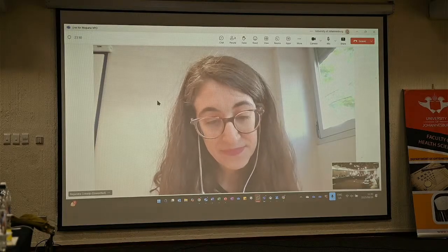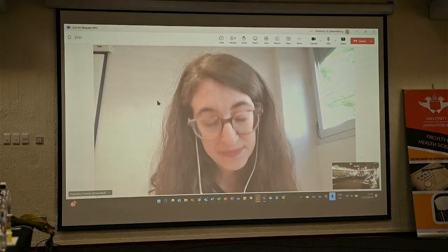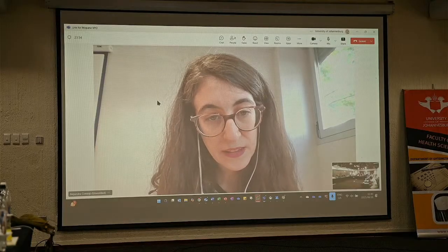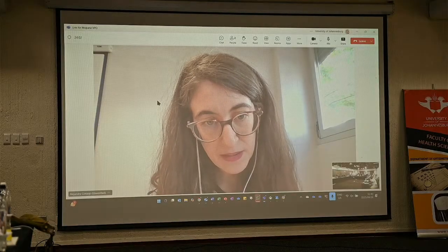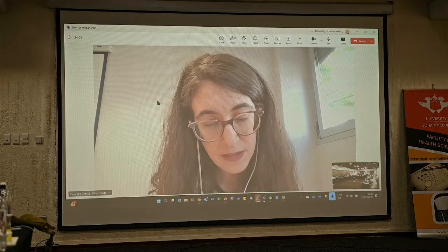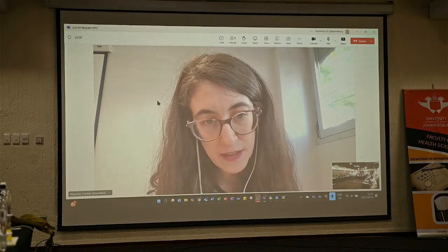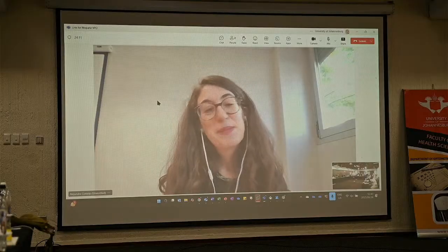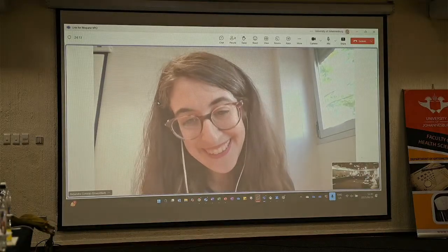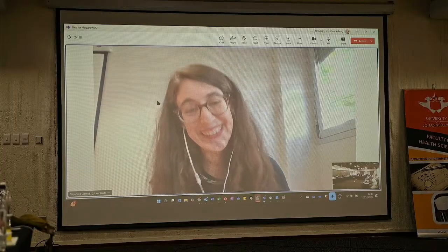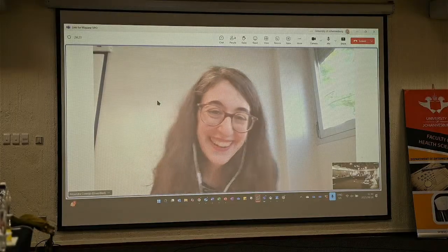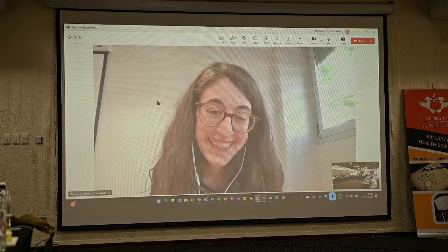I understand it's using white light. But it occurs to me that you might be able to use a colored filter in your imaging system to selectively remove the short wavelength light going into the instrument and reduce the amount of scatter from those lovely blue irises that shine so brightly. Blue eyes shine blue for just the same reason the sky is blue here in Africa: scattered short wavelength light. So maybe you can remove the short wavelengths and reduce your artifact.